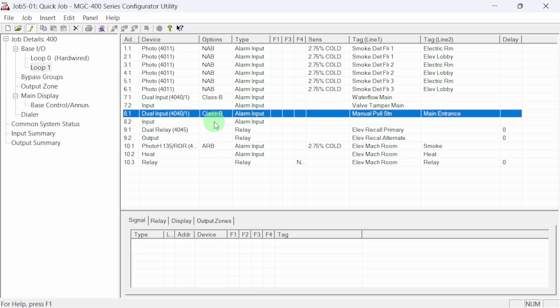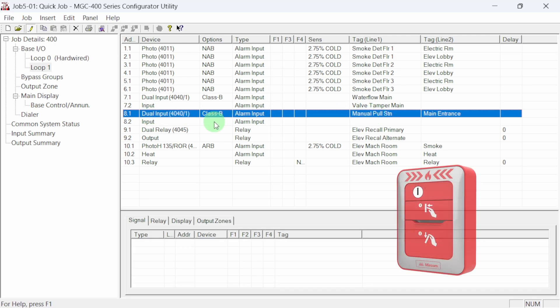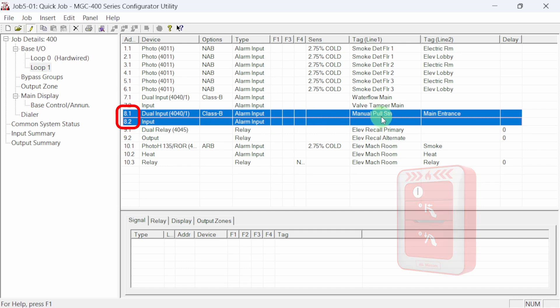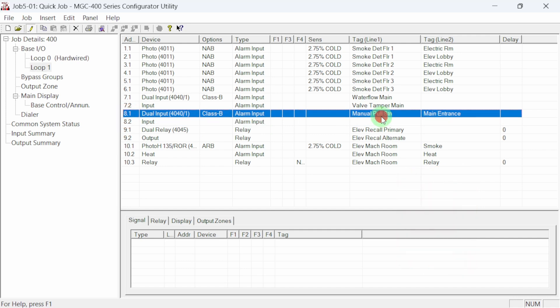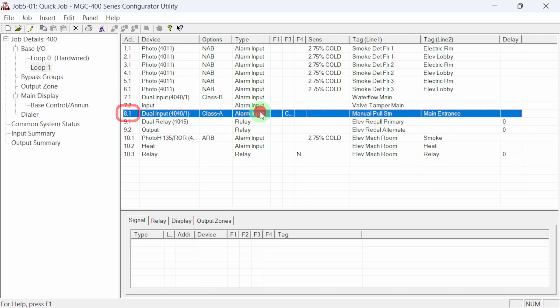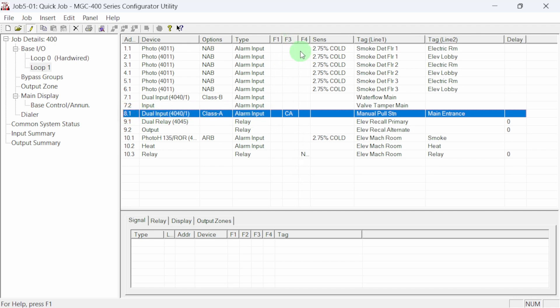If you are installing the single stage pull station, typically used in USA installations, the dual input module needs to be adjusted as class A wired. This is done by selecting the cell in the options column and changing it from class B to class A. The dual module now only has one device point without a sub address. The flag column will also now indicate the device is wired as CA or class A.